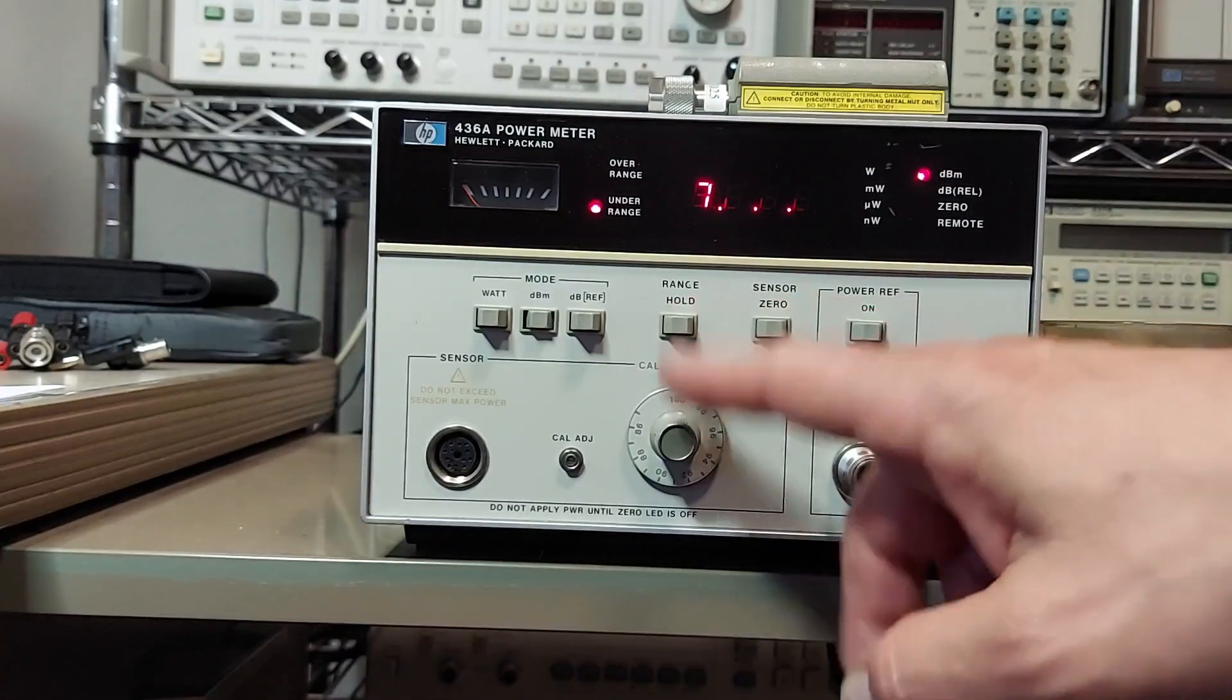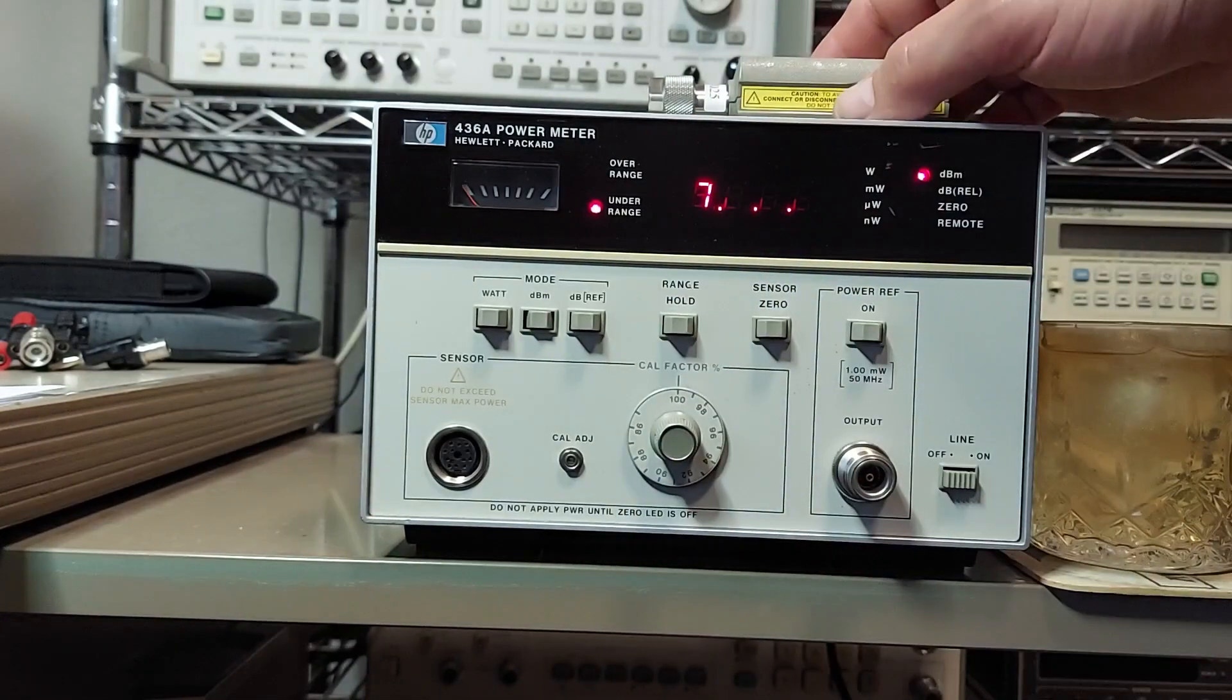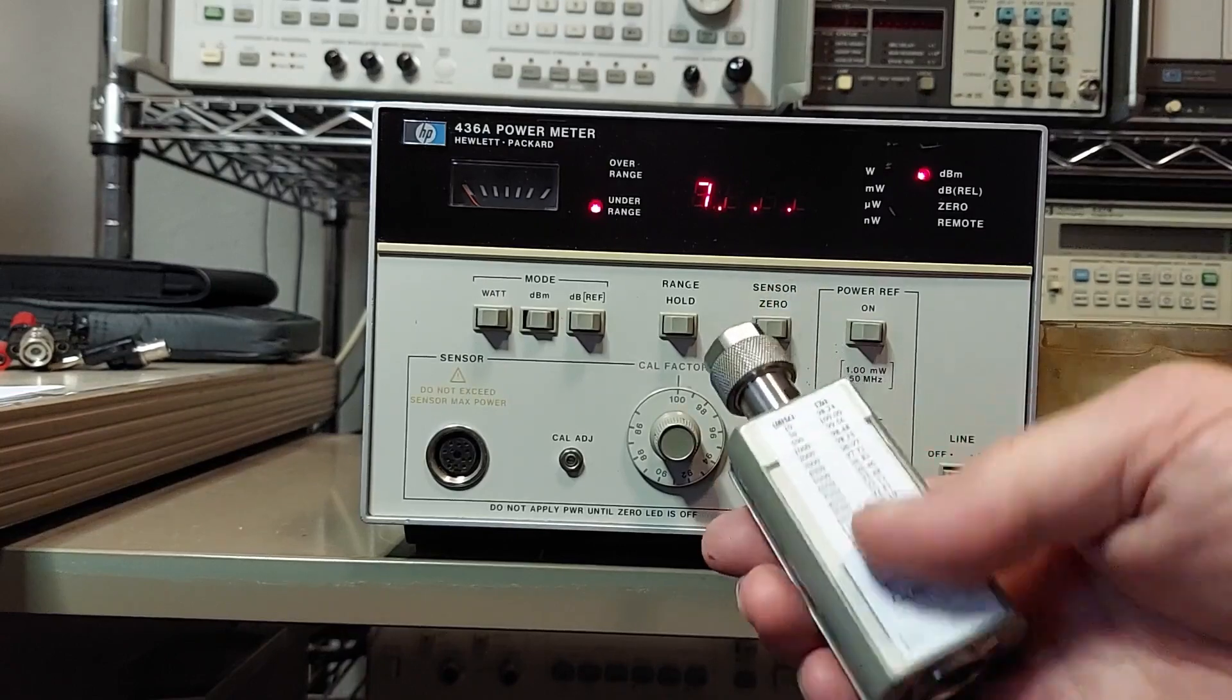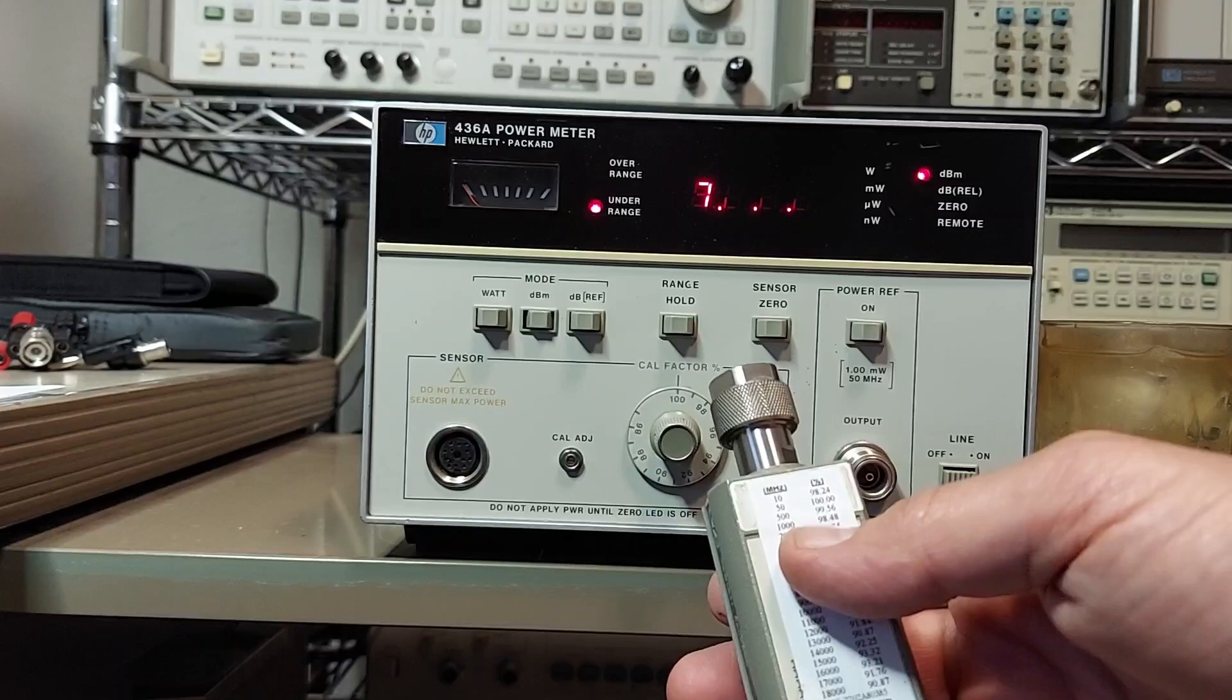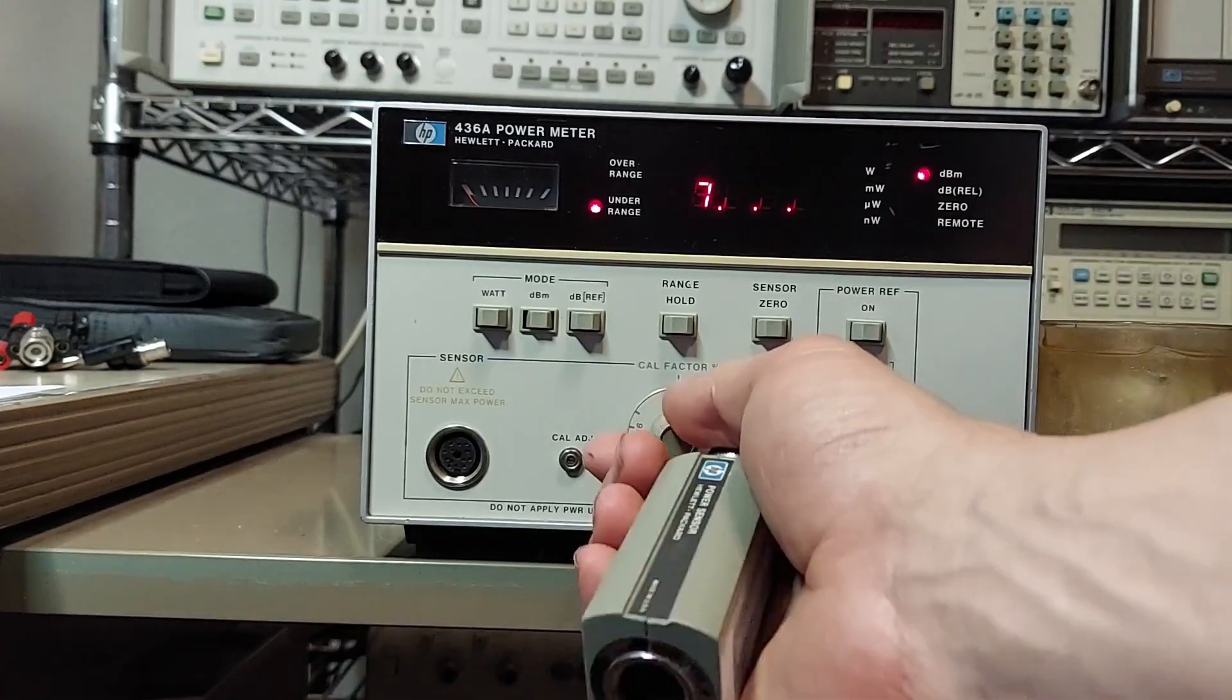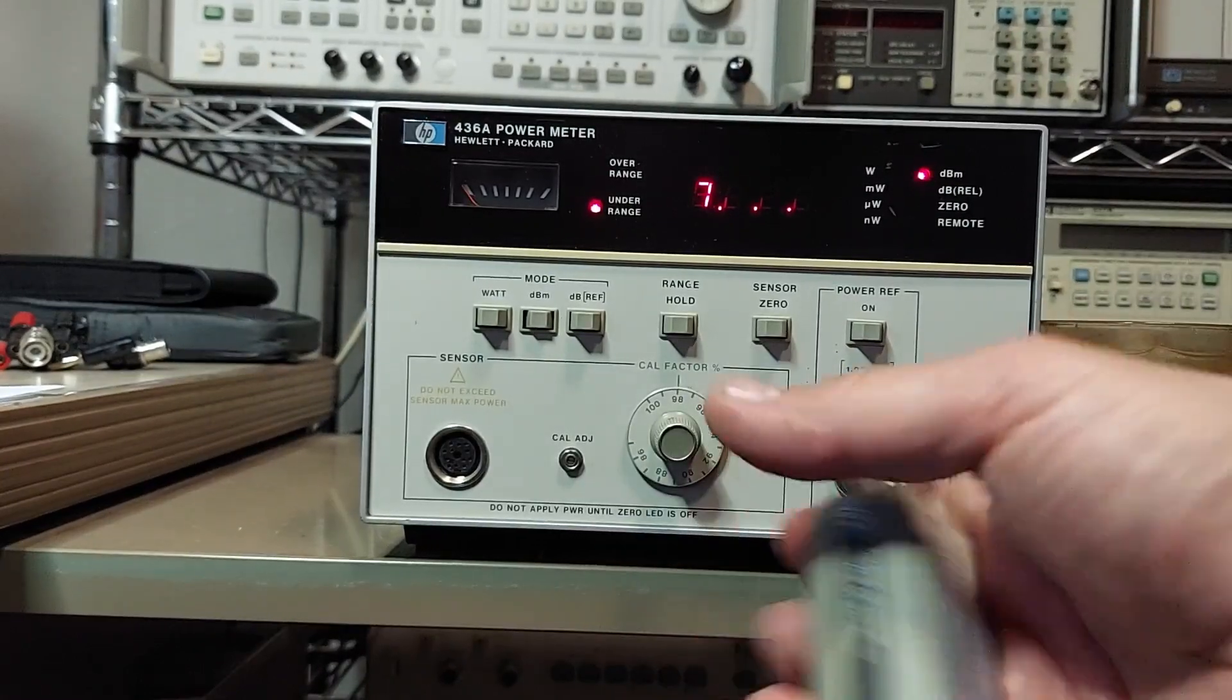Here we've got your calibration factor. This is used depending on what frequency you're on. A lot of these sensors have calibration tables on them. So if I use this sensor and I'm going to be measuring something at one gigahertz, the cal factor needs to be 98.48, so that would mean that I would just set that to 98 and it will correct for the error.